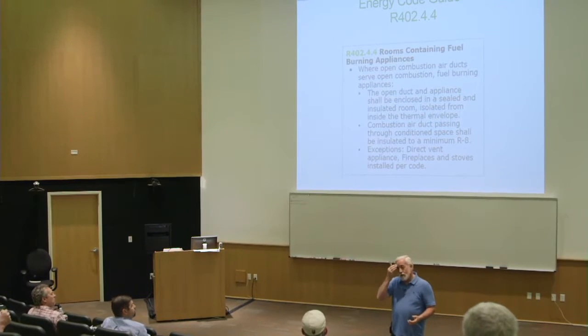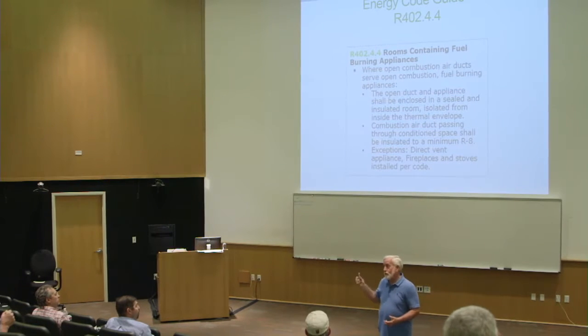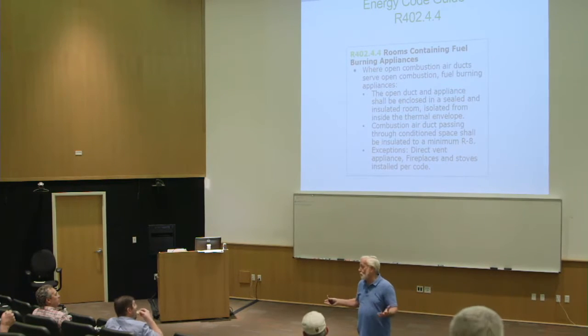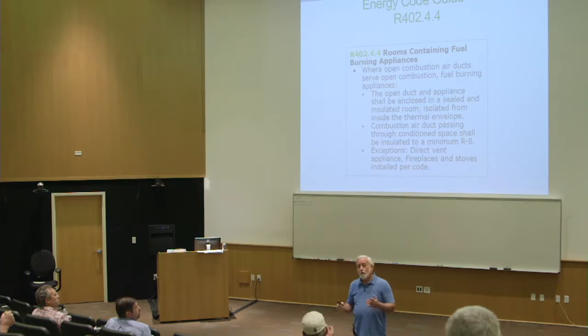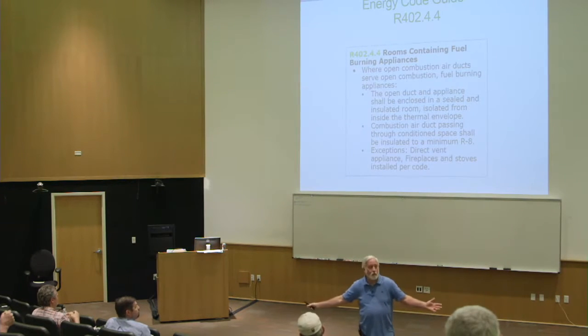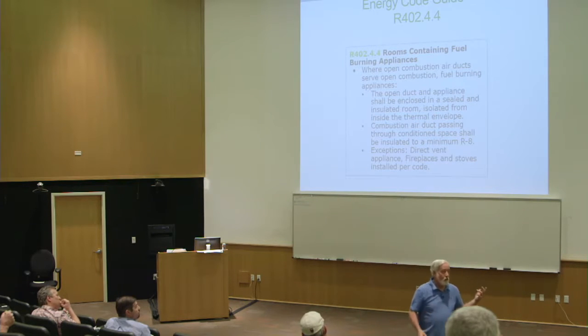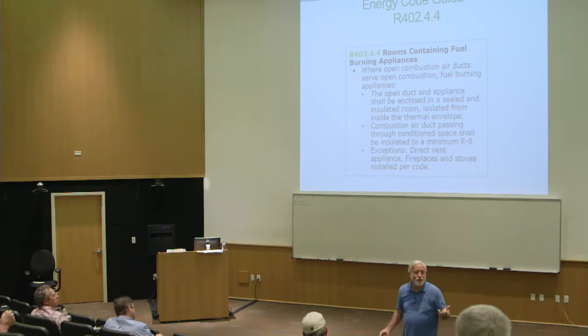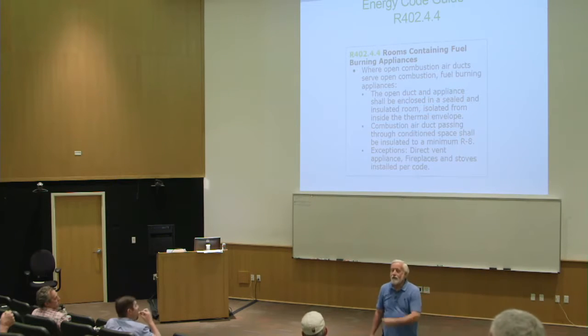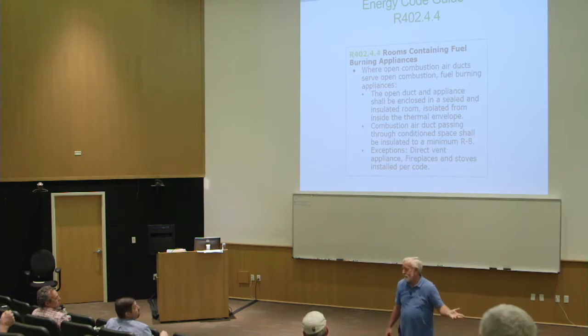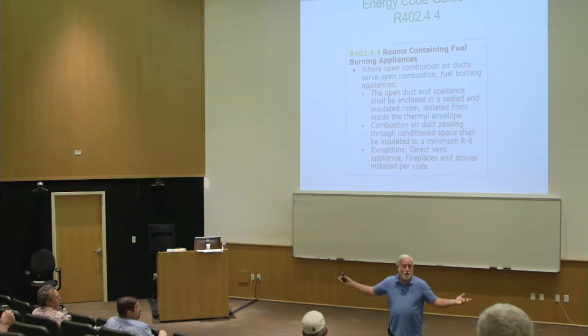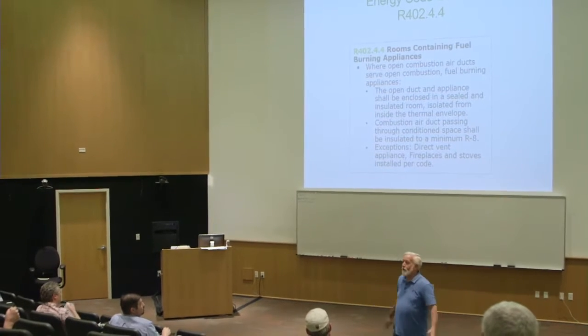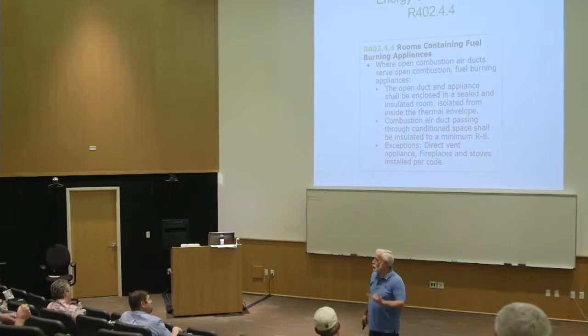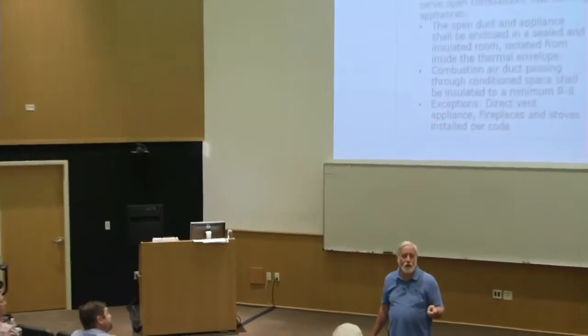And so the only way you could do that, and jurisdictions back when this first started saying, hey, we've got to enclose the room. We've got to isolate that combustion air from the wide open, unfinished basement. Because what do people do? They just go and shove a pillow in it. And we have no combustion air. And there's millions of pillows shoved in combustion air ducts, aren't there? And the combustion air duct code was broken. It required huge amounts of air. My house that I'm in now, because it came horizontally, required 2 10-inch pipes from outside.